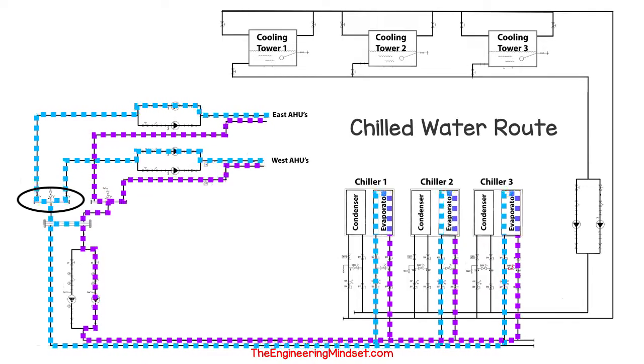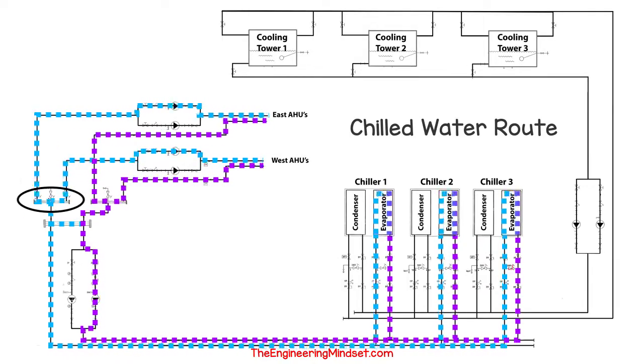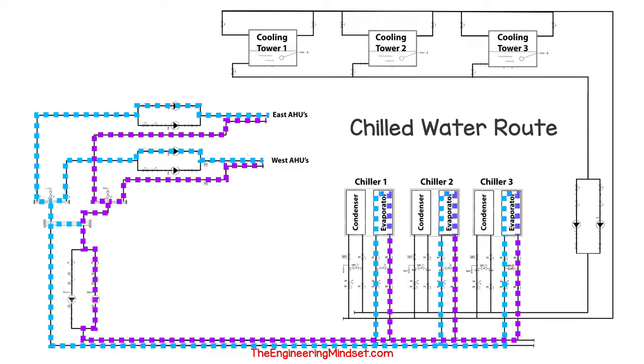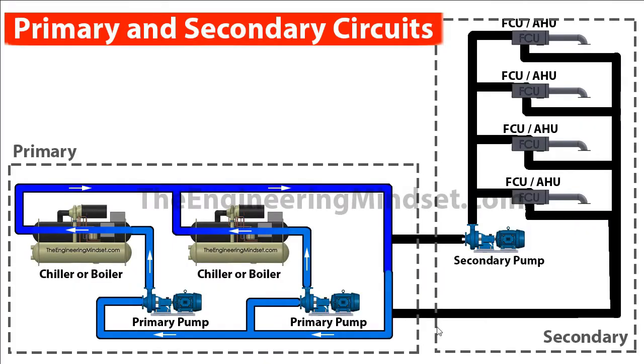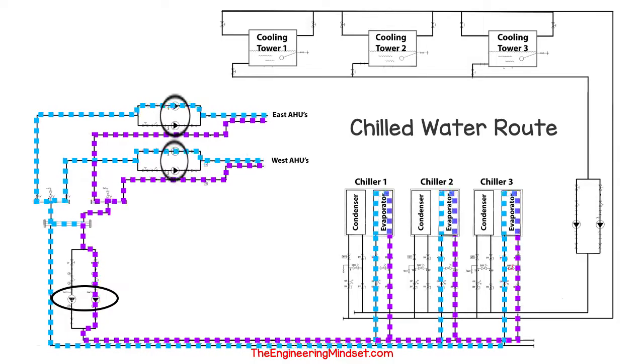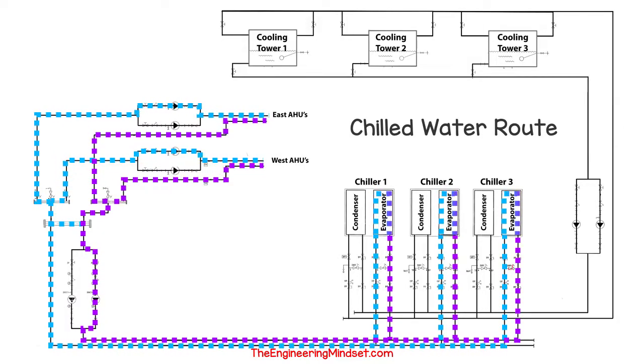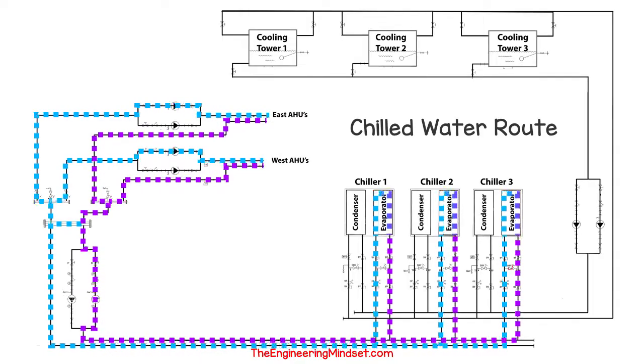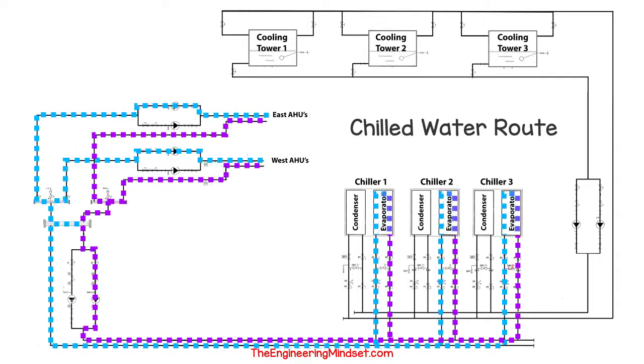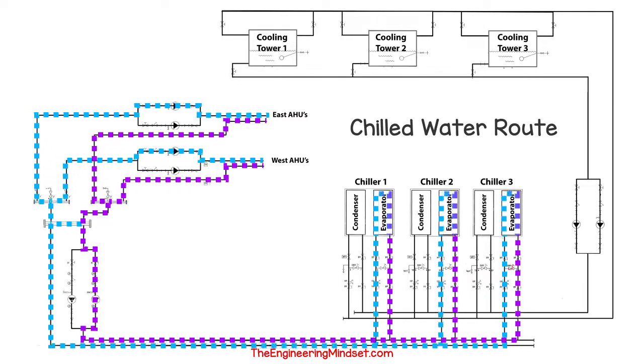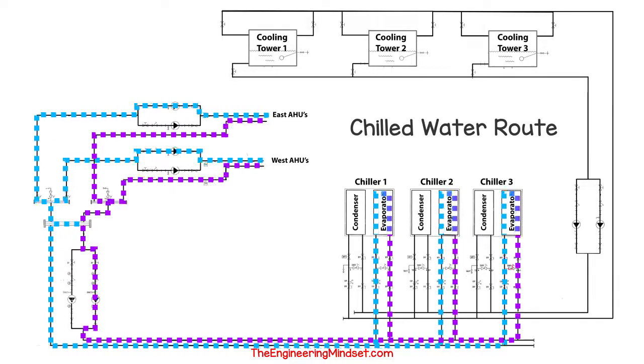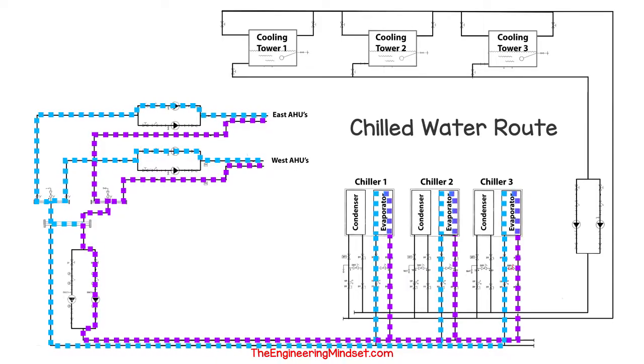You can see on the left that the east and west wing split off from a main header, and the return water joins into another header before returning back to the chillers. This separates the primary and the secondary circuits — we've already covered this in another video, link is on screen. Also notice that only one of the two pumps is running in each pump set. This is because they are using a duty and standby configuration, where one pump is the leader and runs while the other acts as a backup. These roles are reversed every week or so to keep run hours similar.